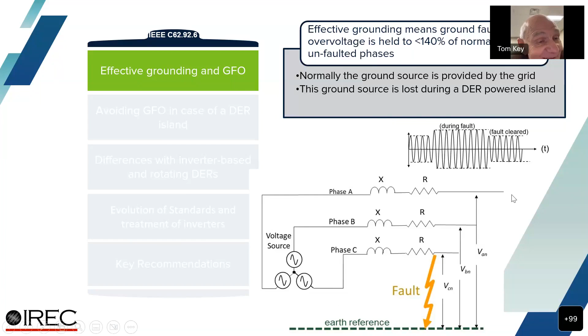The problem is that effective grounding is usually at the substation. So DER, if it's islanding after you're disconnected, can be the source of a full 1.7 overvoltage, which we're not designed for in most systems. So that's it. I think you can go to the next slide, Brian. Sorry about the audio.